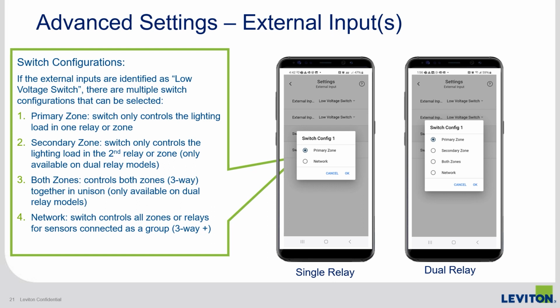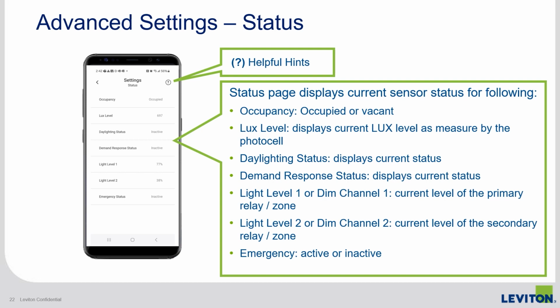The last option is network, and this is used when you have multiple CMS devices linked together wirelessly. In the network option, the switch or dimmer will control all the zones or relays of sensors or room controllers that are wirelessly paired together. When connected to a sensor or room controller, you can check the current status by clicking on the status caret. From there, you can check the following: occupancy status, current lux level and whether it's in daylighting mode, demand response is active, current light levels, and you can see if emergency is currently active.